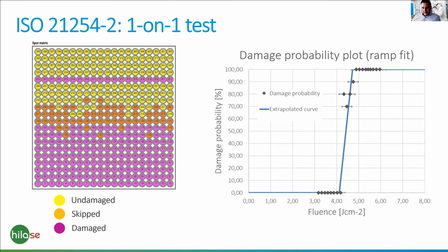You are observing whether the exposed position is damaged or not. And if not, you can increase the energy on further spots until damage is observed.